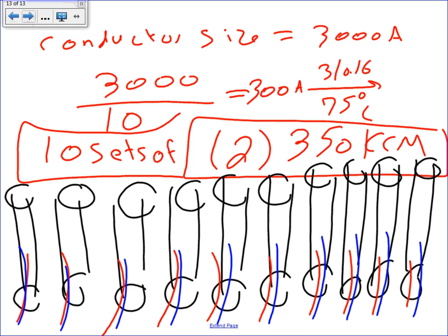What type of conduits? For this system, most likely you're coming from underground PVC. Can I use EMT? Bring it on. Can I use rigid? Yes. Most likely a system like this, guys, will be coming from underground. So you're going to use PVC schedule 40 or 80. 80 is preferred for utilities for protection. So most likely this will be real life schedule 80 PVC underground ducts.